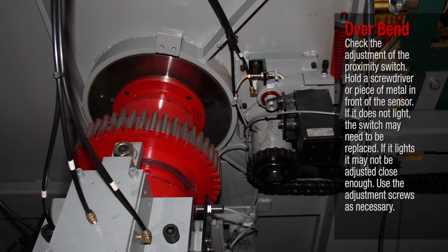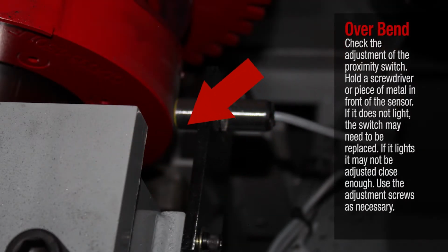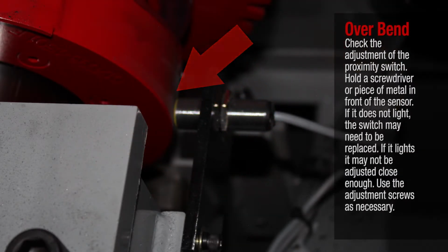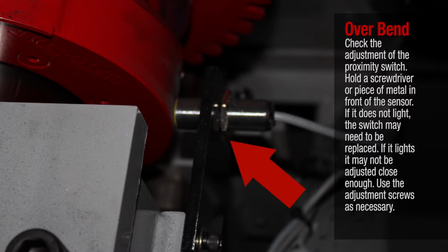Overbend. Check the adjustment of the proximity switch. Hold a screwdriver or piece of metal in front of the sensor. If it does not light, the switch may need to be replaced. If it lights, it may not be adjusted close enough. Use the adjustment screws as necessary.